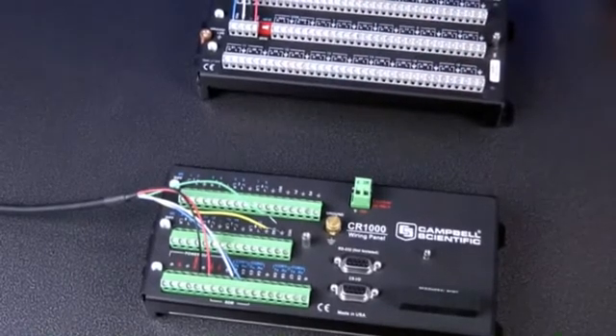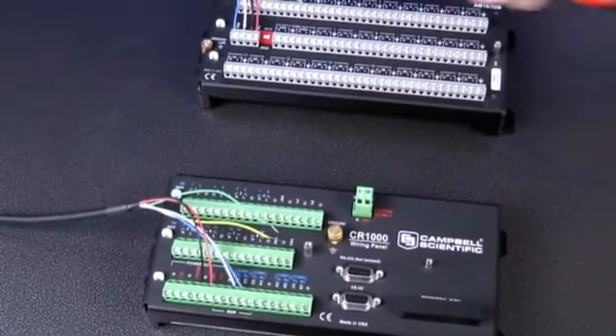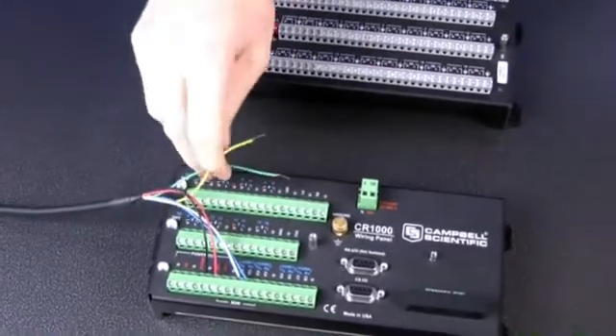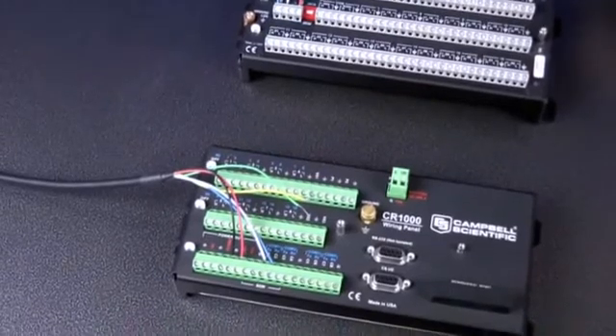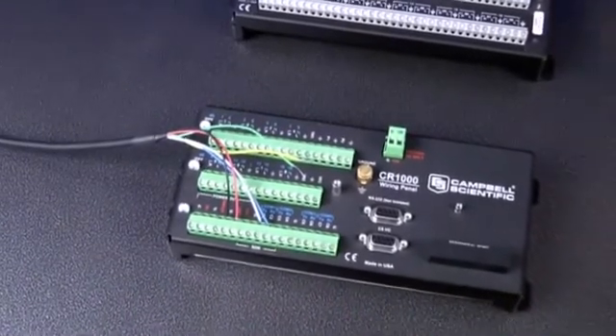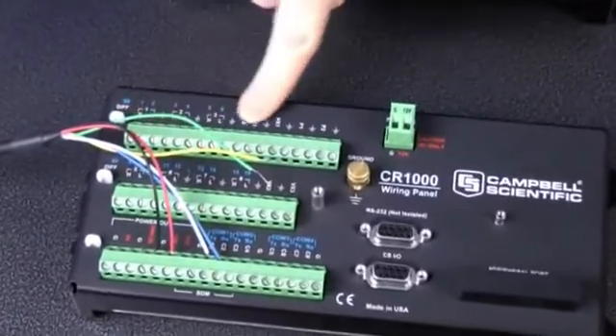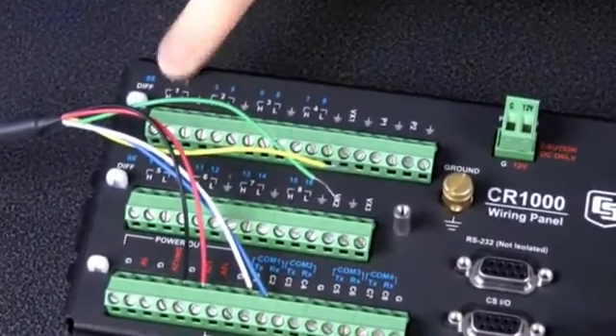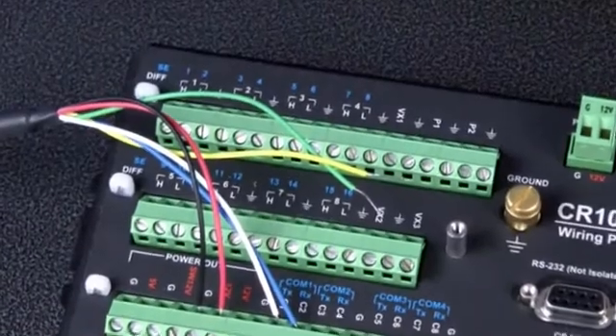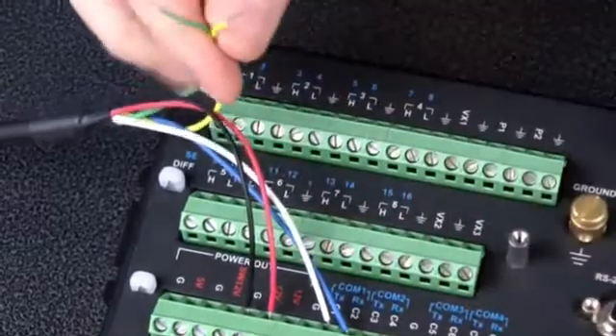We'll move down to the CR1000. Right, so I have my power connected to my multiplexer. I also have my control signals. That's C1 and C2 going to clock and reset. The last bit of wiring that we need between the two devices are these two extra wires here. They are going to connect the actual sensor signals from the multiplexer to the datalogger. So it's an analog multiplexer. It's for analog sensors. So they need to go into our analog inputs. Again, it depends on your program. The example program that I'm going to be using is using 1H and 1L to measure the sensors. So I'm going to connect these two wires, green into 1H and yellow into 1L.